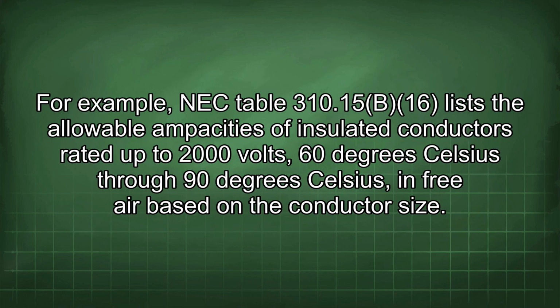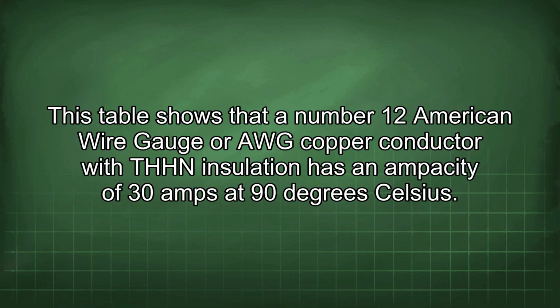For example, NEC Table 310.15(B)(16) lists the allowable ampacities of insulated conductors rated up to 2000 volts, 60 degrees Celsius through 90 degrees Celsius, in free air based on the conductor size. This table shows that a number 12 American wire gauge or AWG copper conductor with THHN insulation has an ampacity of 30 amps at 90 degrees Celsius.